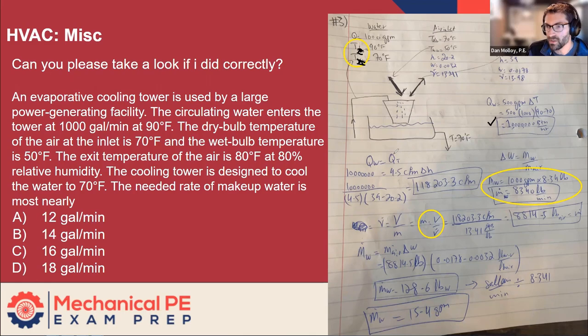And then you set that equal, you said the amount of heat that's being removed from the water is the amount of heat that's being taken into the air. And you represented that as 4.5 CFM Delta H, which is absolutely correct. And then you identified that both the air inlet and outlet are fully defined states, you know, temperature and wet bulb or temperature in RH, which gives you the ability to find out enthalpy specific humidity and a specific volume, which is going to be good to know. And then the next thing that you did is you wrote this equation, the mass flow rate of water that's being removed from the condenser water through evaporation into the air is equal to M dot air Delta humidity ratio. And that is absolutely correct.